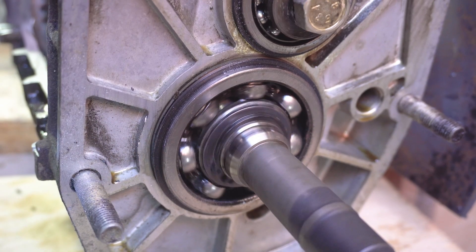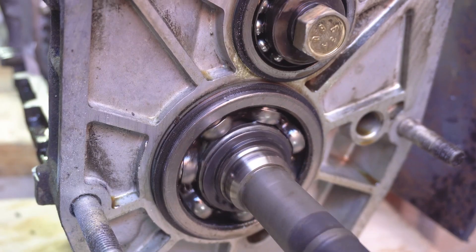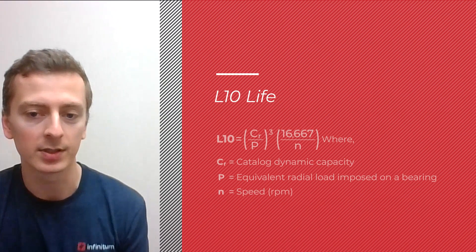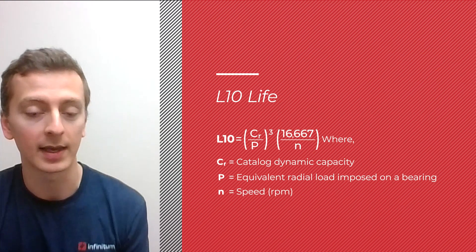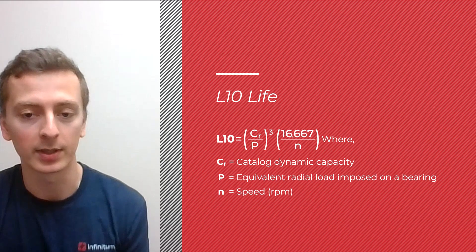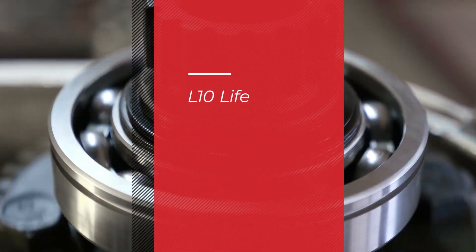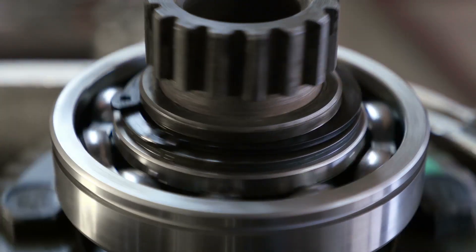The usual life rating for bearings in industrial applications is called the L-10 life. Simply put, L-10 life is a calculation to determine, with 90 percent reliability, how many hours a bearing will last under a given load and speed.